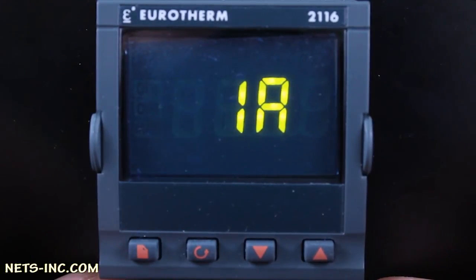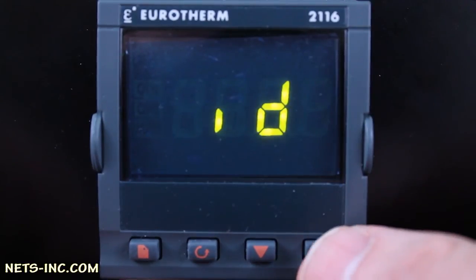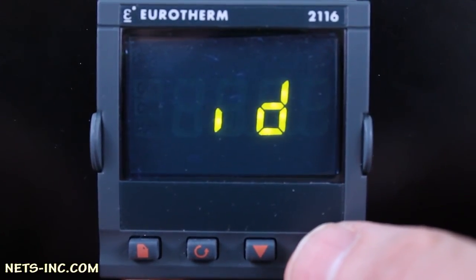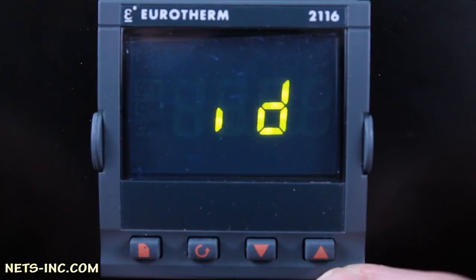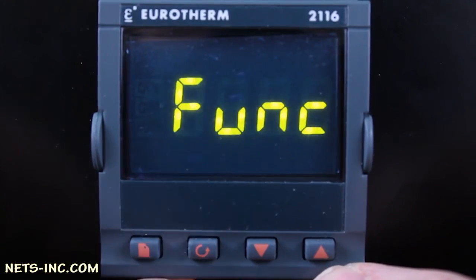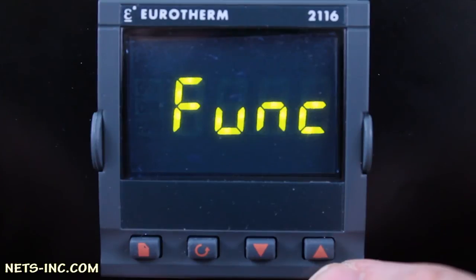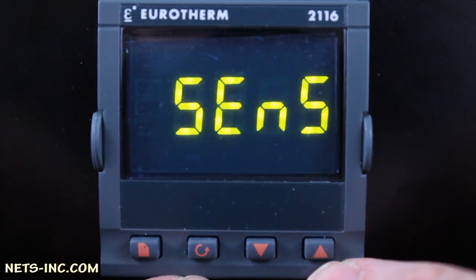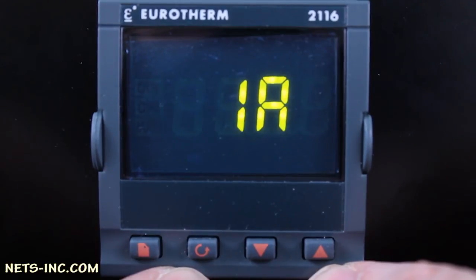Next, press the page key once to advance to the 1A list. This is the 1A logic output on terminals 1A and 1B. This output will be set up in this example as the heating output. Press the scroll key once to drill down into the 1A setup list. The display will read ID. Press the up arrow to verify that the ID equals LOG or logic. Press the scroll key once and the display will read FUNC. Press the up arrow key repeatedly to change the FUNC to HEAT. Press the scroll key and the display will read SENSE. Press the up arrow to ensure that the display reads NOR or normal. Press the scroll key once and you are back to the display reading 1A.